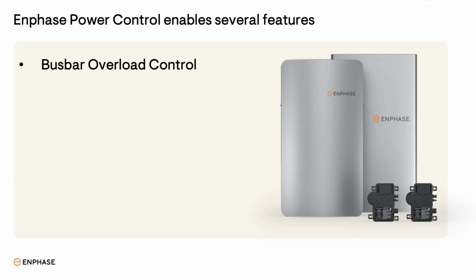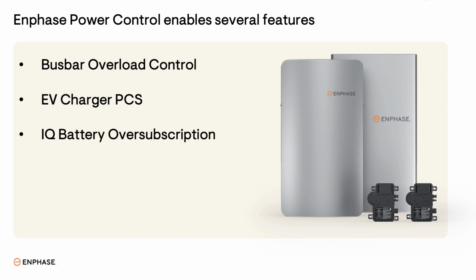While avoiding main panel upgrades is the most common use of Enphase Power Control, it also offers the following features. EV Charger PCS. This feature intelligently manages EV charging to prevent main breaker trips during periods of high home energy consumption. This feature also helps avoid service upgrades due to a high-power EV charger exceeding the load that a service is meant to support. IQ Battery Oversubscription. This allows homeowners to install more battery capacity while limiting the power. This is useful to get around breaker limitations in the IQ System Controller or IQ Combiner.